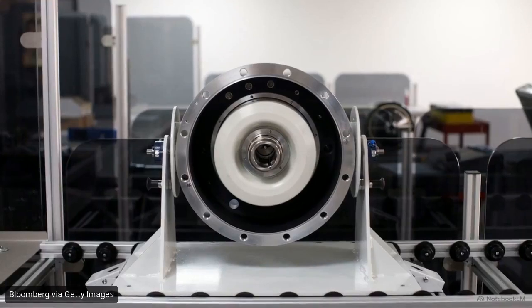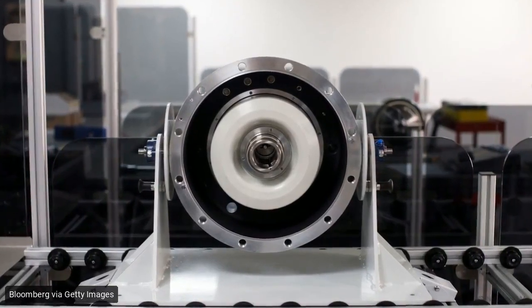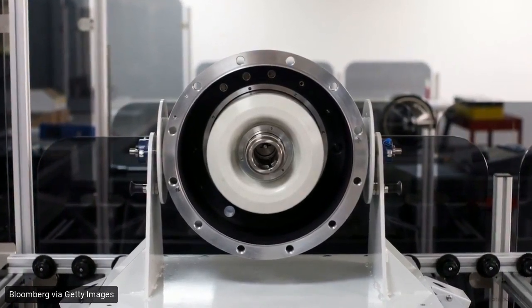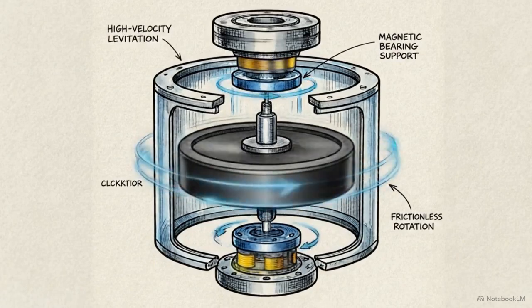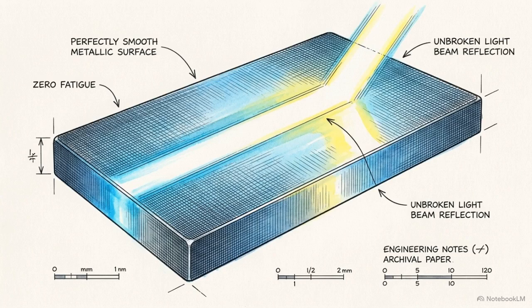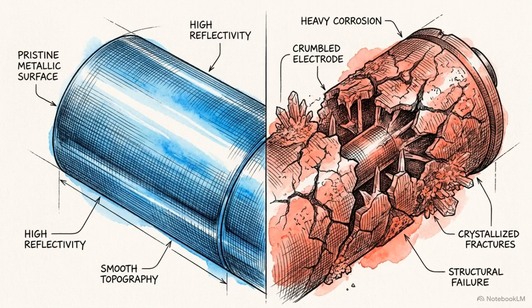For microsecond frequency regulation, the primary kinetic solution is the mechanical flywheel system. Flywheels utilize highly engineered mechanical hardware designed to operate with near-zero friction. The mechanism stores kinetic energy by suspending a rapidly spinning mass inside a strict vacuum enclosure, using magnetic bearings to eliminate physical resistance. The specific advantage of a flywheel over a BESS is its sheer durability. It can absorb and discharge massive power spikes indefinitely without suffering the chemical degradation that limits battery lifespans.